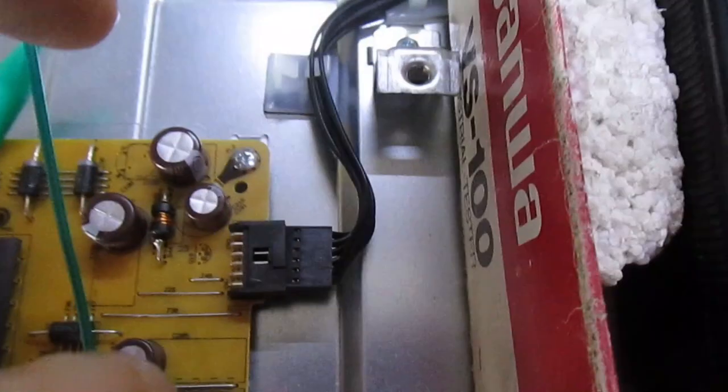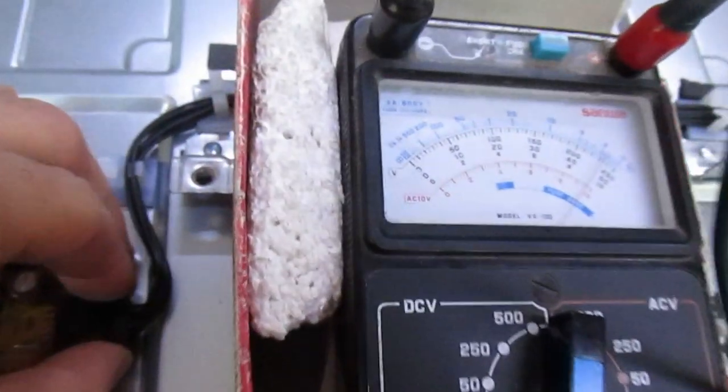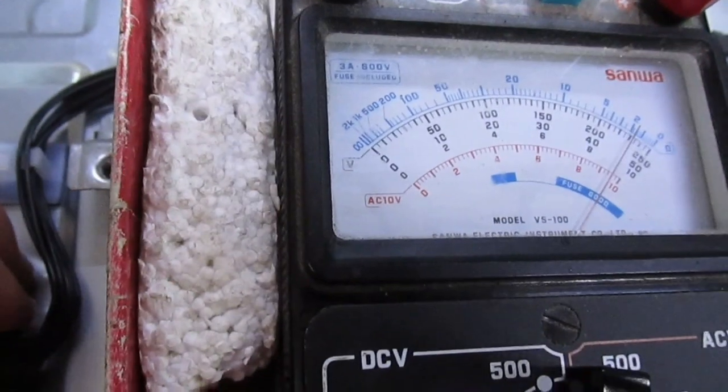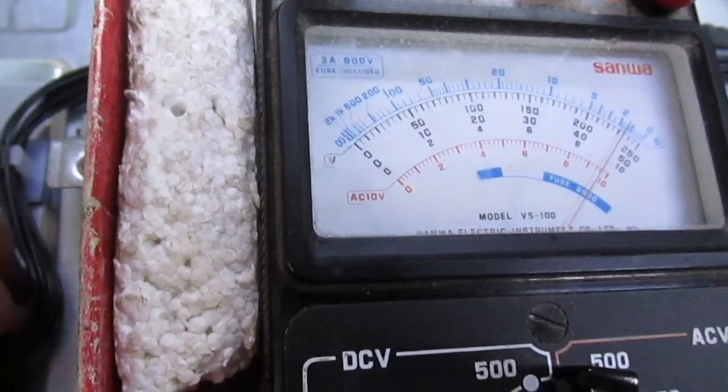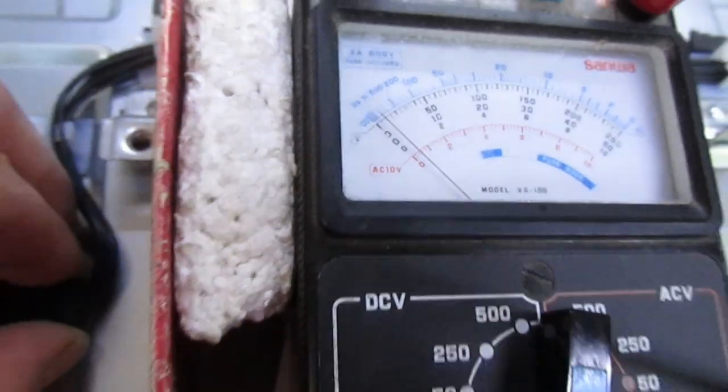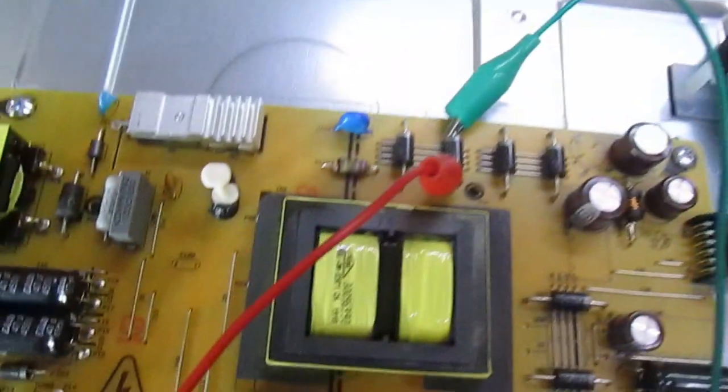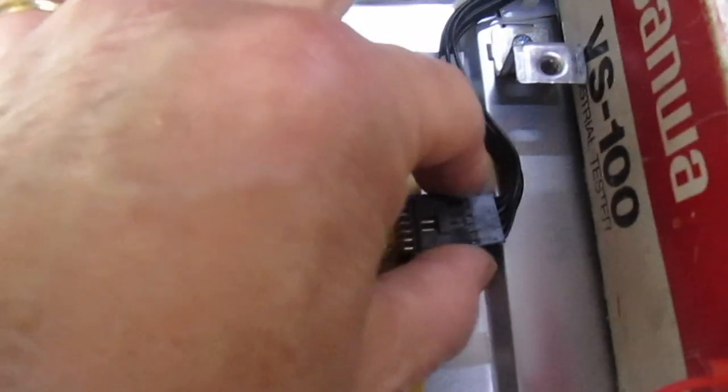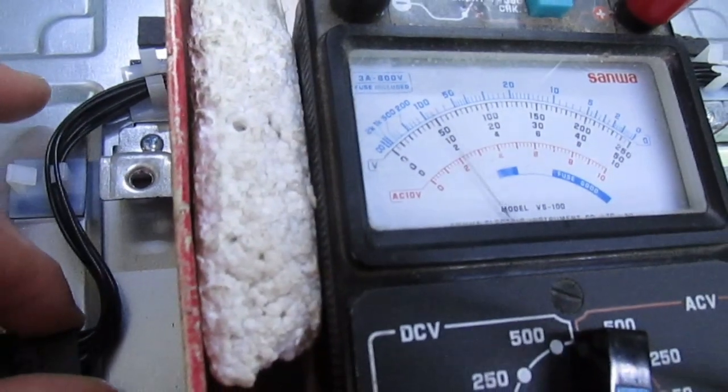Now we unplug this connector going to the main board. If you watch the meter, I unplug the connector and the short goes away. So it's not actually the diode that's faulty, it's a short circuit on the main board that this connects to.